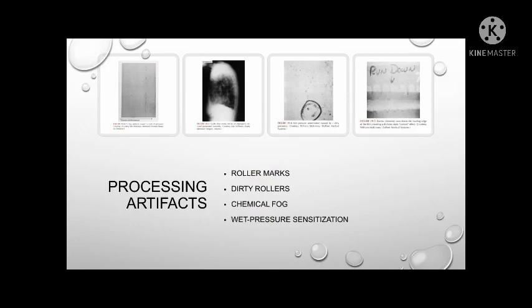Another category is processing artifacts. Most are pressure-type artifacts caused by the transport system of an automatic processor. Pressure-type artifacts usually sensitize the emulsion and appear as higher optical density. A scraped or removed emulsion due to lack of developer hardener may appear as lower optical density. First among processing artifacts are roller marks. In an automatic processor, the transport system uses rollers through which the film travels to different processing tanks.